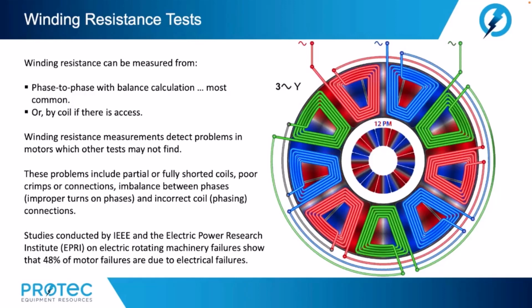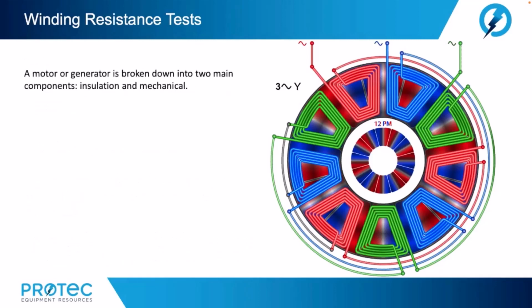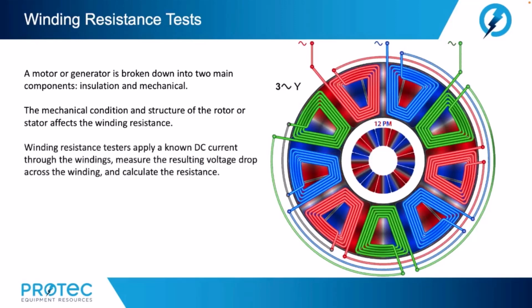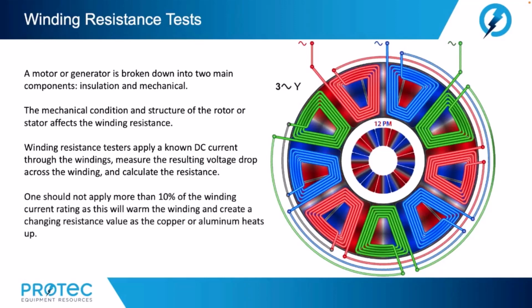failures show that 48% of motor failures are due to electrical failures. A motor or generator is broken down into two main components, insulation and mechanical. The mechanical condition and structure of the rotor or stator affects the winding resistance. Winding resistance tests apply a known DC current through the windings, measure the resulting voltage drop across the windings, and calculate the resistance. One should not apply more than 10% of the winding current rating, as this will warm the winding and create a changing resistance value as the copper or aluminum heats up.